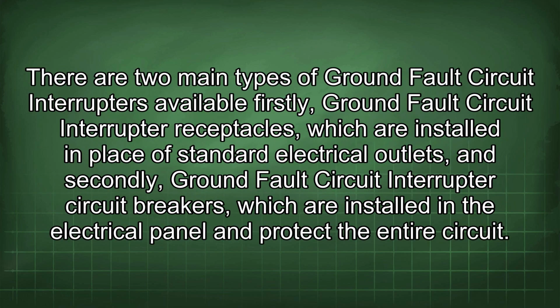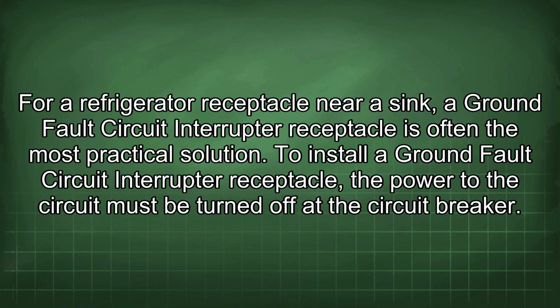There are two main types of ground fault circuit interrupters available. Firstly, ground fault circuit interrupter receptacles, which are installed in place of standard electrical outlets, and secondly, ground fault circuit interrupter circuit breakers, which are installed in the electrical panel and protect the entire circuit. For a refrigerator receptacle near a sink, a ground fault circuit interrupter receptacle is often the most practical solution.